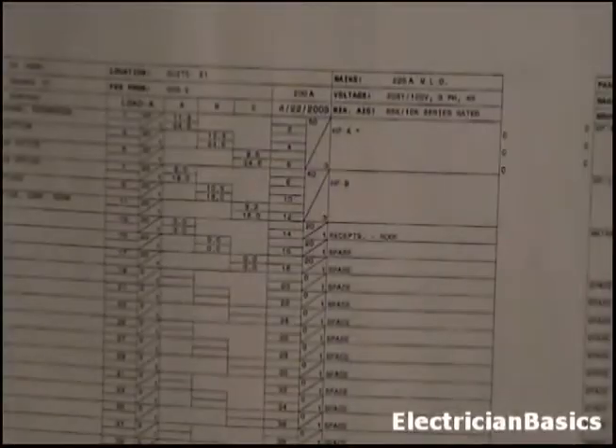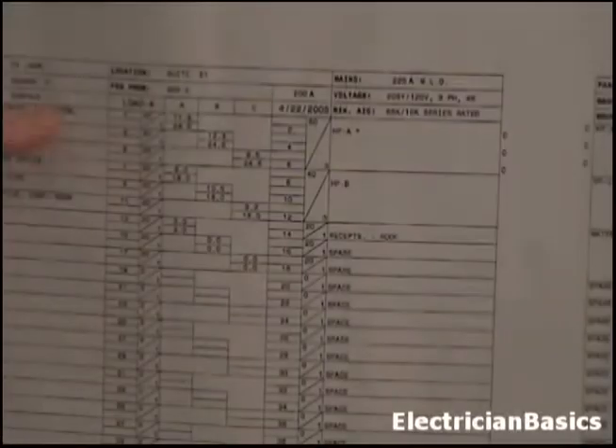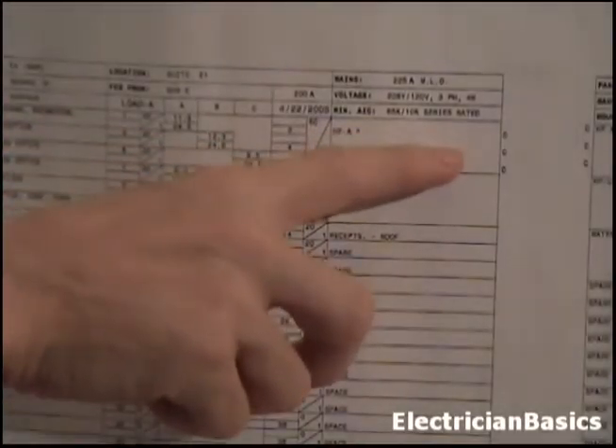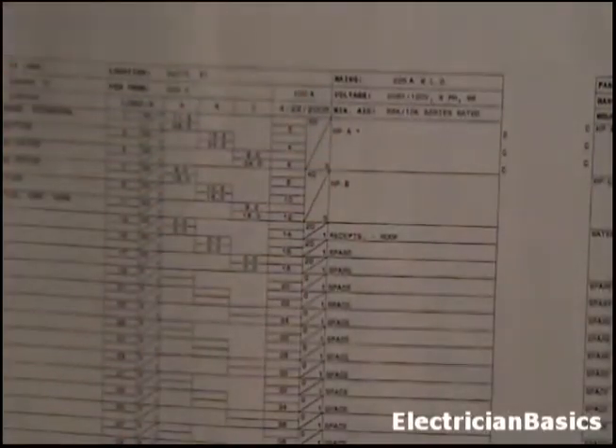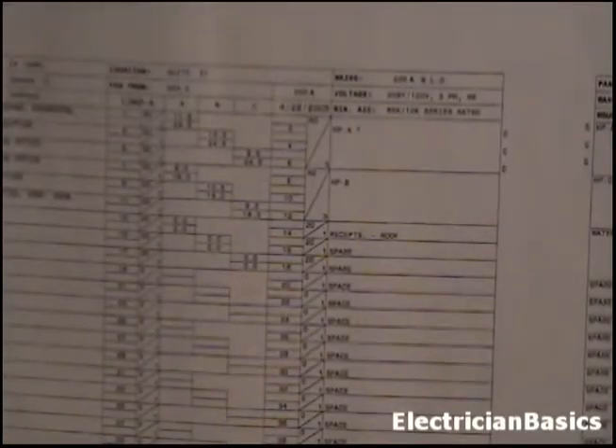Now, what I want you to do at this point in time, on these 2 panel schedules, I want you to find all of the 2-pole breakers. Now this is a single pole breaker over here. We had 3 of them. This is a 3-pole breaker. So I want you to find the 2-pole, all the 2-pole breakers on these schedules, and I want you to find out the circuits. I want you to find out the breaker sizes. I want you to find out what they control. And also I want you to find out what phases that those circuits are on. So pause the video right now, find all of the 2-pole breakers, and then come back.